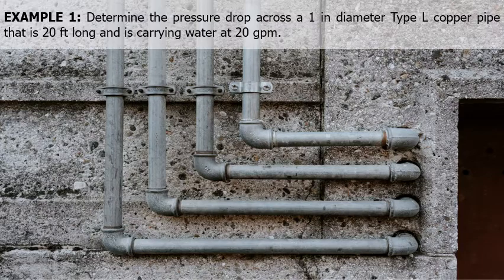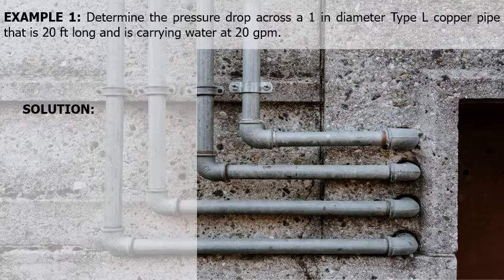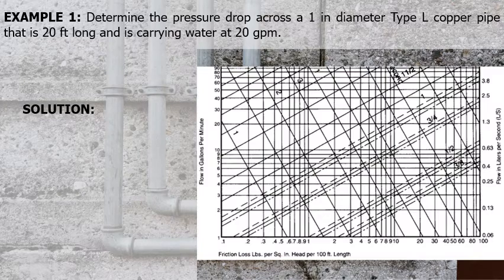Let's have an example. Determine the pressure drop across a 1-inch diameter type L copper pipe that is 20 feet long and is carrying water at 20 gallons per minute. In this problem, we will be using Figure 13.6, which is a pressure drop chart for smooth pipe or copper tubing.